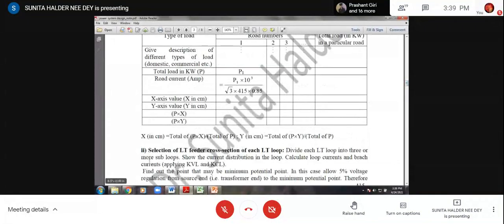Now the next step is selection of LT feeder cross section of each loop. Say in your sub-block there are some scattered loads and there is one transformer somewhere. You have to supply this load from this transformer with the condition that the distributor should go through a road, right? Let's see this.